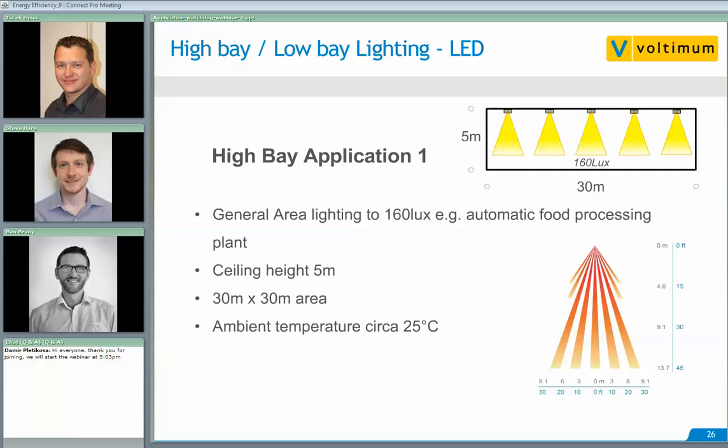A question on induction lighting: induction wasn't covered but it is a viable option for high bay or open area lighting — a high output, long life light source. However, there are some drawbacks: it's quite a bulky fixture and you potentially run into issues with EMI. The gear can also be a lot lossier. Induction high bays are still readily used but, in my personal opinion, not as common as the three light sources discussed today.